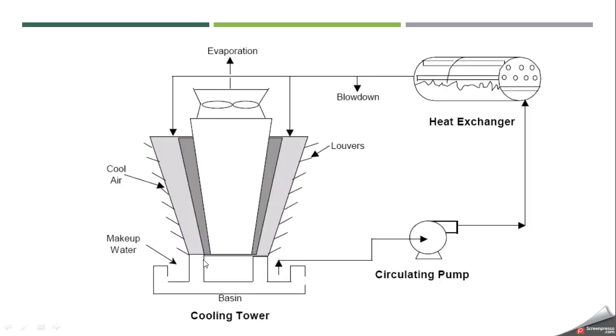The schematic of the open recirculating system shows a basin from which cold water is taken and sent to the heat exchanger. The water absorbs heat from the process, some is blown down, and the rest is sent to the cooling tower. In the cooling tower, water is sprayed and mixed with cooled air. The air takes heat from the water, some water evaporates, and the remaining cooled water returns to the basin to be reused.